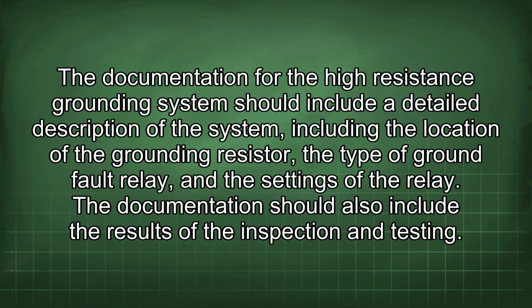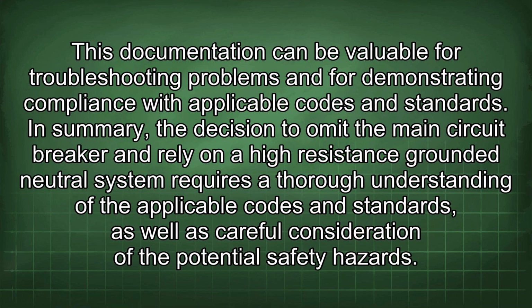The documentation for the high-resistance grounding system should include a detailed description of the system, including the location of the grounding resistor, the type of ground fault relay, and the settings of the relay. The documentation should also include the results of the inspection and testing. This documentation can be valuable for troubleshooting problems and for demonstrating compliance with applicable codes and standards.